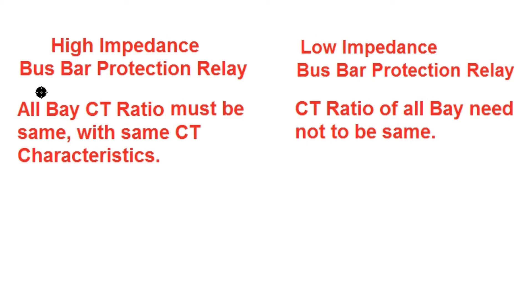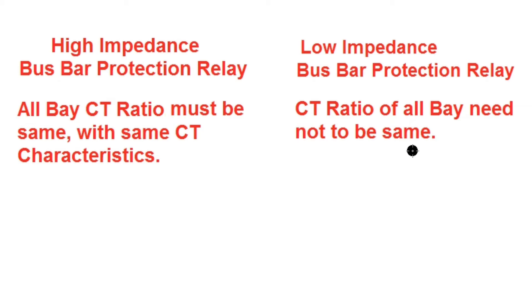In case of high impedance bus bar protection relay, all bay CT ratios must be the same with the same CT characteristics — that is, the knee point voltage and the CT resistance must be equal. In case of low impedance bus bar protection relay, the CT ratio of all bays need not be the same, and the characteristics of all the CTs need not be the same.